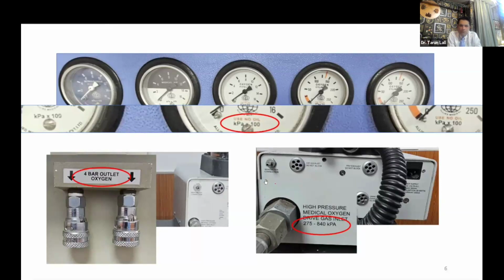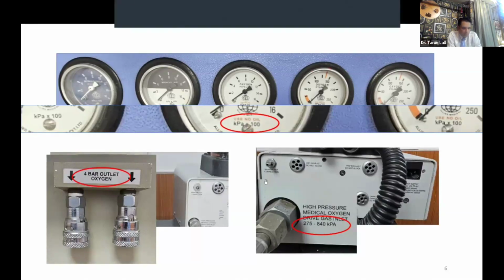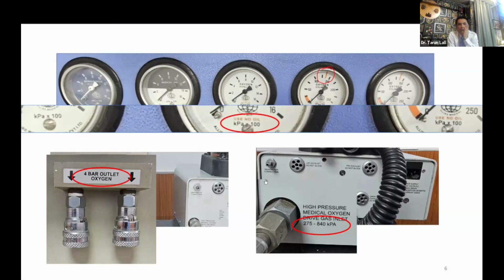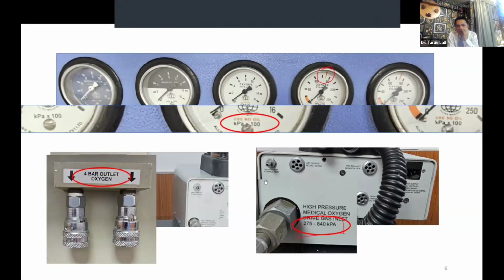So 100 kPa we know is 1 bar. 150 kPa is 150 into 100 kPa, you can see it marked here. That is your full oxygen cylinder. So 150 into 100 kPa is your full oxygen cylinder, which means about 150 bar. 4 bar is your pipeline supply. And now if I have to see how much is this 275 to 840, I know that it is about 2.75 to 8.4 bar.